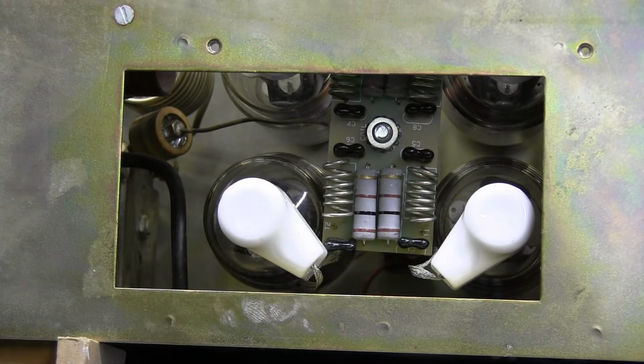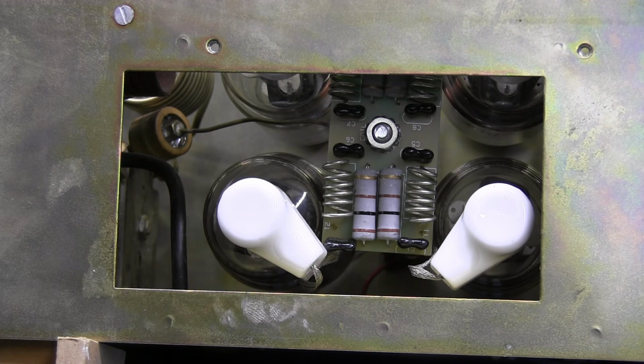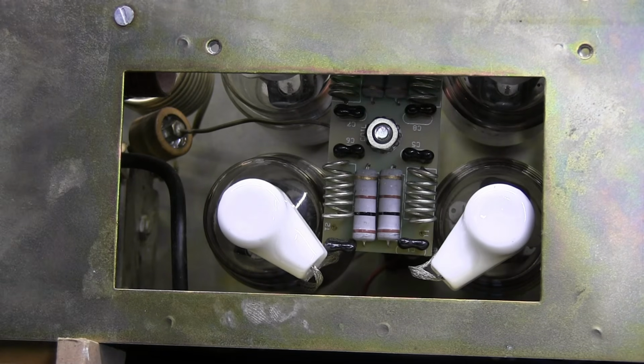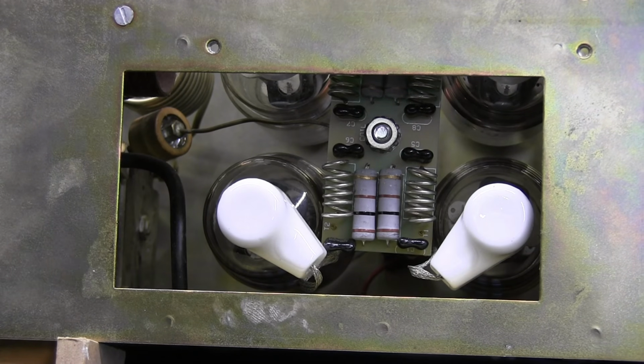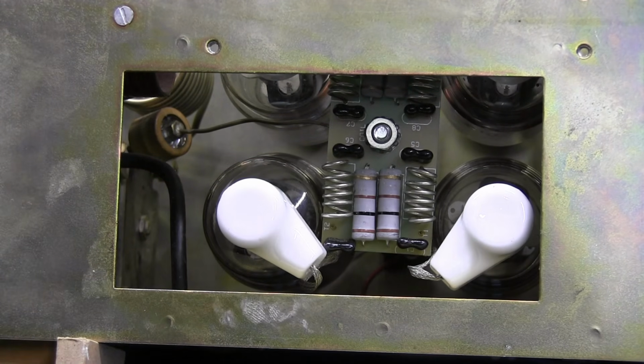I was thinking the RF choke had been changed, but after looking at it, it's an original style RF choke, so that has not been upgraded. Maybe I need to order a replacement RF choke to put in there - this one looks okay, so we might just order one to have as a spare in case something's wrong. But it is good to see they have the new suppressor board installed.